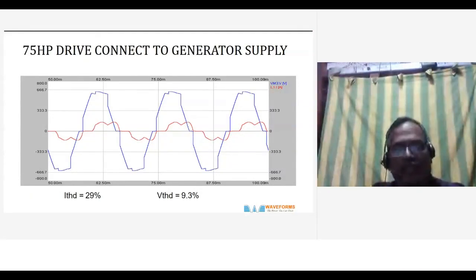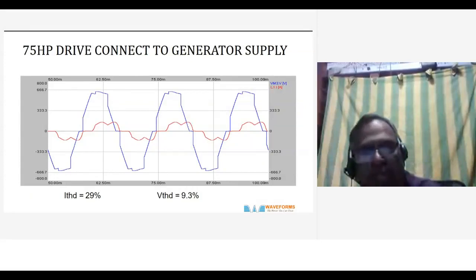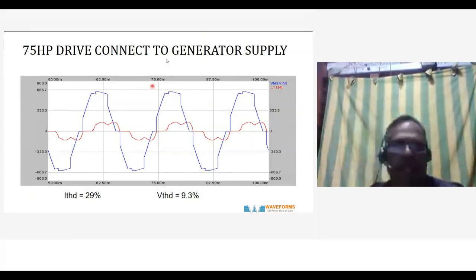So the same thing, if you connect it to a generator supply, you see the voltage also getting distorted. So the voltage distortion also depends on the impedance value or X/R ratio of the transformer. With a high X/R ratio, the distortion will be less. But if it is low, then the distortion will be more. Similarly, in a generator, the voltage distortion can be more. So normally you will have to overrate your generator by say 2x or 3x depending on the level of performance.